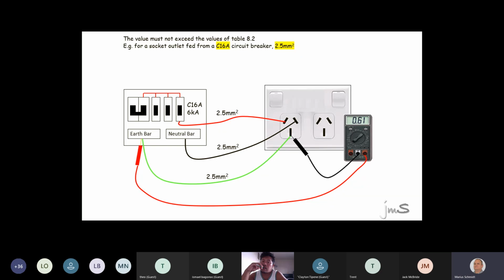If you take your TPS 2.5 out of your van, it's a roll of what, 50 meters, 100 meters? Take your ohm meter and measure earth to earth, beginning to end. See what you're going to get, 400 meters. That will be a good exercise. And you can say half of it will obviously be half the resistance, a quarter of it will be that, and you can work out what will give you 0.61. And that will give you the length as well. Isn't that okay? You take 100 meters and you can work yourself back. That is physically. But in this case, a bit different.